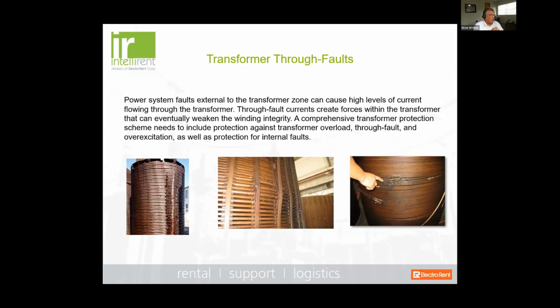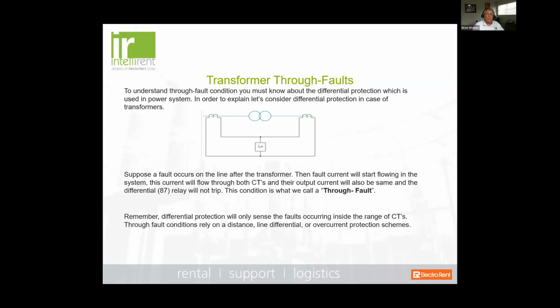But one of the things you have to consider is that when you have a fault external to the transformer, that's not something necessarily that the protective relay system is going to see in terms of taking the transformer out of service. So to understand the difference between a through fault and an internal fault, think about where your current transformers are located. You have a current transformer on the primary side, and then on the secondary side, and we're looking for that current differential to exceed its minimum pickup.